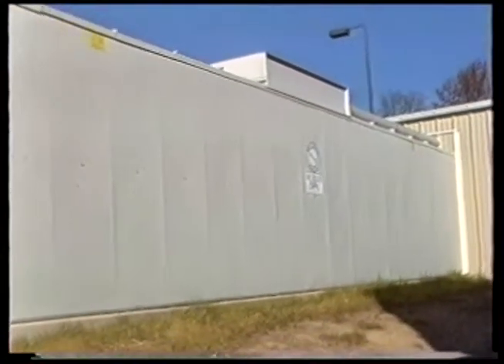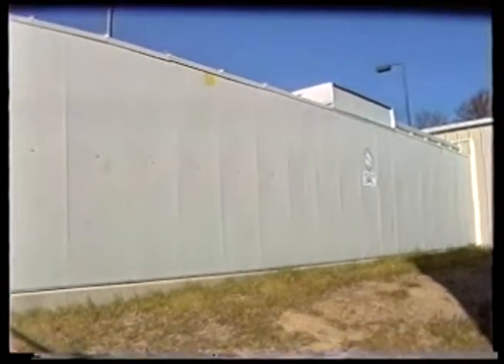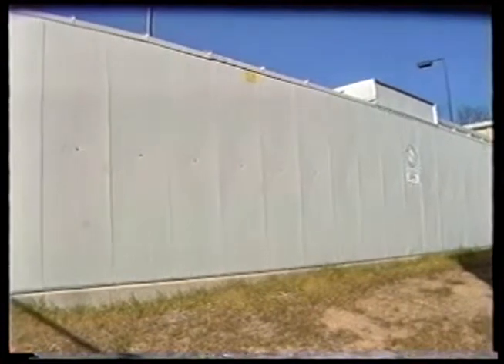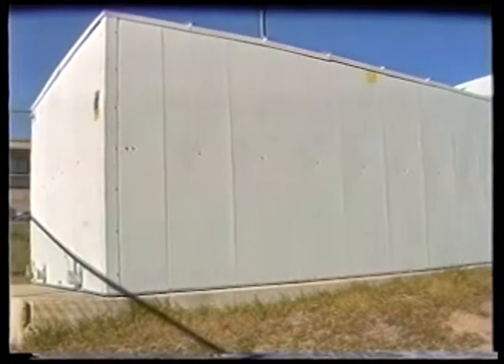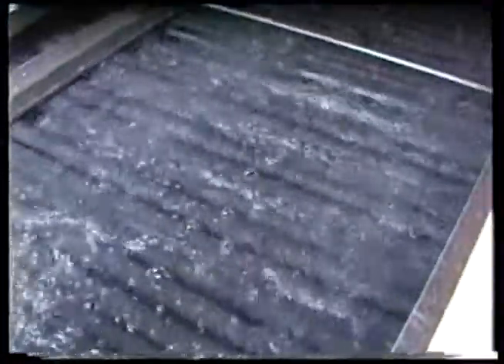This ice builder and storage module is an ice-on-coil design. It's made of heavy-gauge, hot-dipped, reinforced galvanized steel panels welded to be watertight. It is corrosion protected. It is insulated with expanded polystyrene insulation with vapor barriers. It employs a unique patented serpentine steel coil tested to 350 psig air pressure underwater.